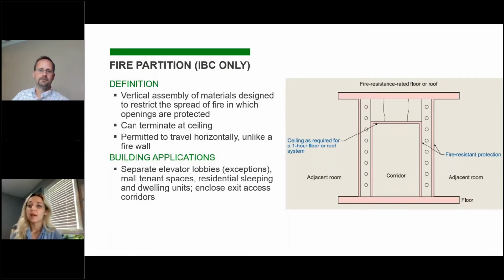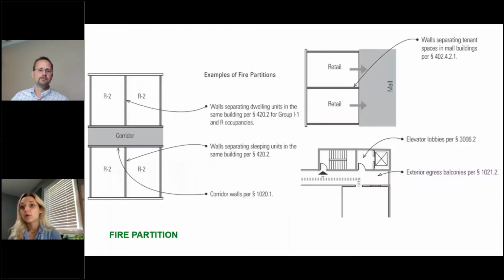All right, so again, moving another step towards the less hardy of the requirements, we run into fire partitions. This is a term that is only defined in the IBC. NFPA exclusively uses the term fire barrier, and they don't use the term fire partition. In the IBC, it's described as a wall restricting the spread of fire, openings protected, but it can terminate at a ceiling, which is different than a fire barrier. It can also travel horizontally, so you could run it up and over in an L shape to act as a rated ceiling. And we'll see this code term used in rated elevator lobbies, separating mall tenant spaces, sleeping rooms in hotels and apartments and whatnot, and rated corridors.